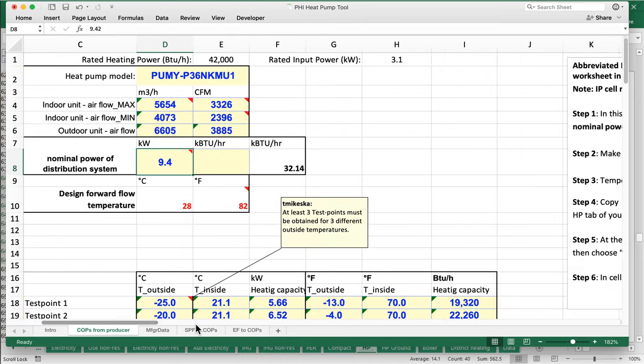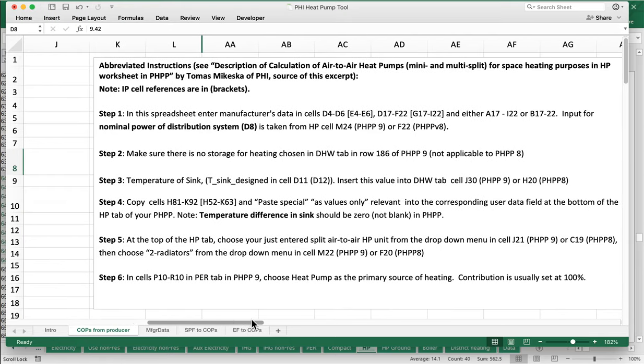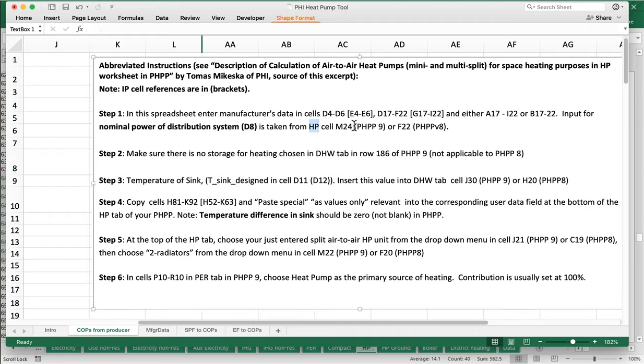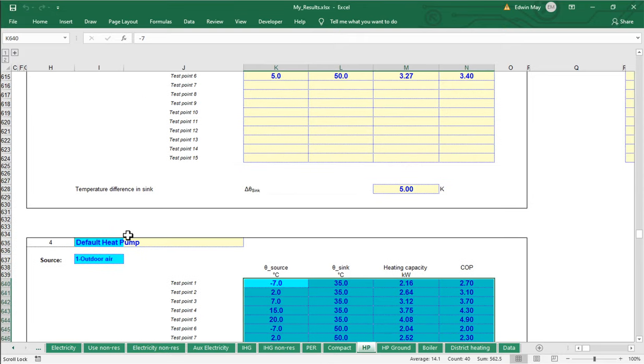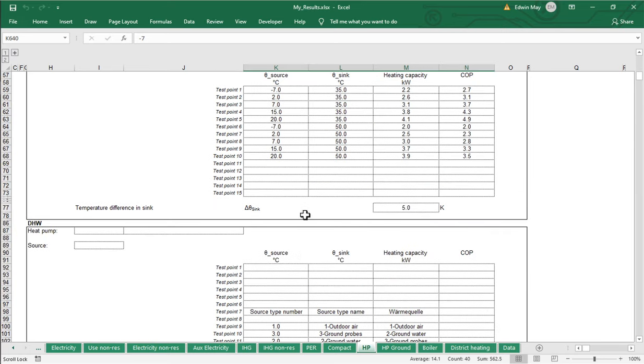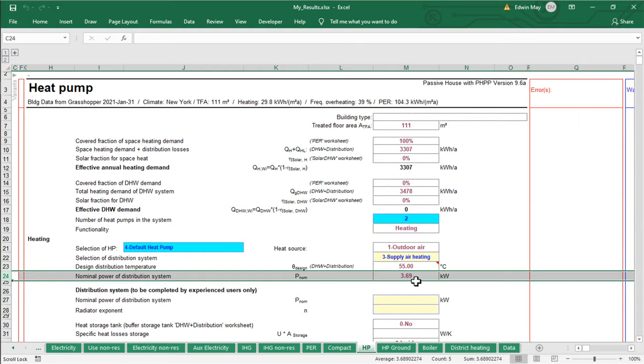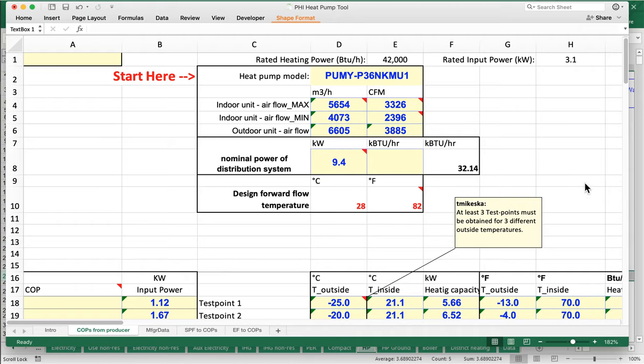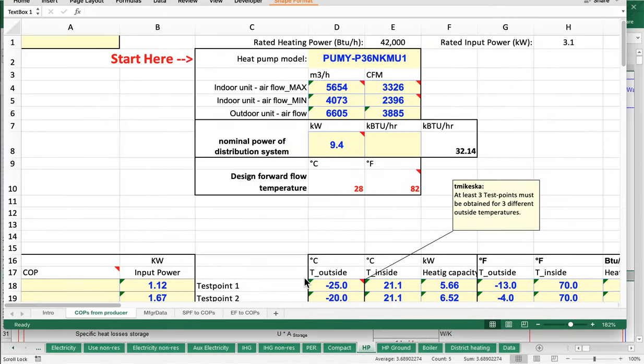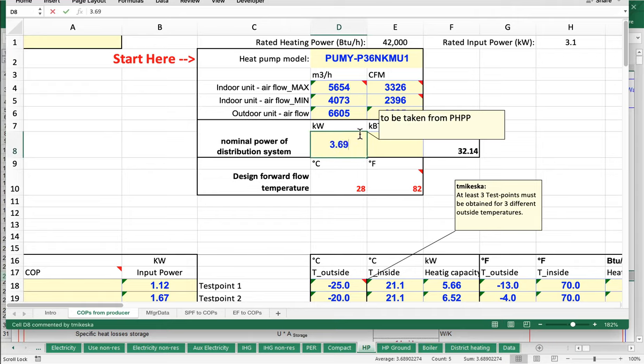Looking at the instructions, nominal power of the distribution is taken from the PHPP heat pump worksheet, cell M24. That cell gives us a calculated value of 3.69 kilowatts, based on all our other PHPP inputs. So we go back to the heat pump tool and type in 3.69, and that will shape how all the other calculated values are generated.